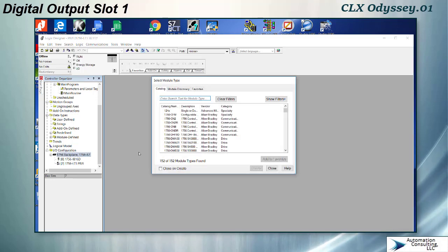Now we're going to put in an output card, more or less the same procedure. Everything associated with ControlLogix is 1756 bulletin. And the I's are inputs, the O's are outputs. They are all digital for OBs and IBs. OAs are generally AC, 74 volt to 265 volts AC. We're going to pick a fairly standard OB16.